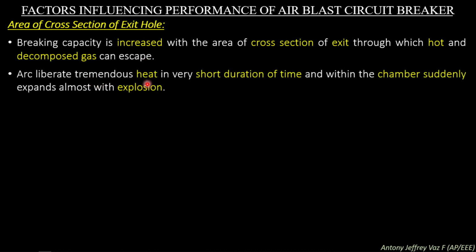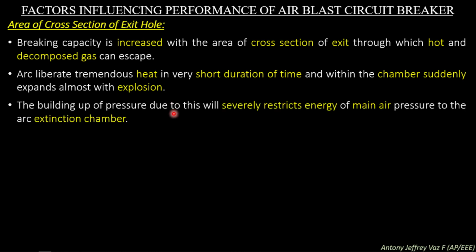Arc liberates tremendous heat in a very short duration of time, and within the chamber suddenly expands almost with explosion. So if the arc is initiated at once, a sudden liberation of high temperature in the air occurs. So this will create an explosion effect inside the chamber suddenly. The building up of pressure due to this will severely restrict energy of main air pressure to the arc extinction chamber.